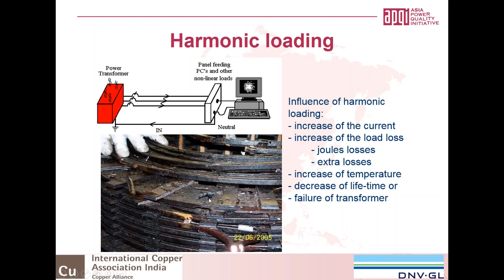Normally you will see the extra losses within a transformer are not evenly distributed within a winding, but they are mostly on the top of the winding or on the below side of the winding. But on the top of the winding there is always the highest temperature, so in case you have a harmonic problem, it will mostly arise on the top of the winding somewhere. In this case it was the same.